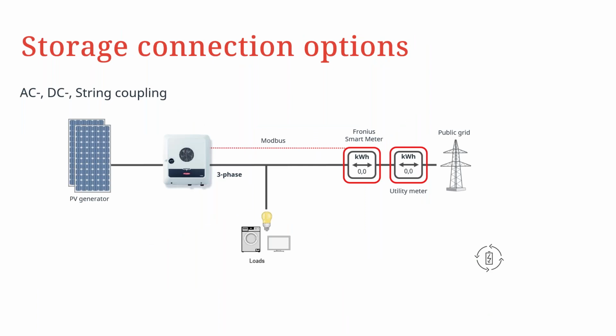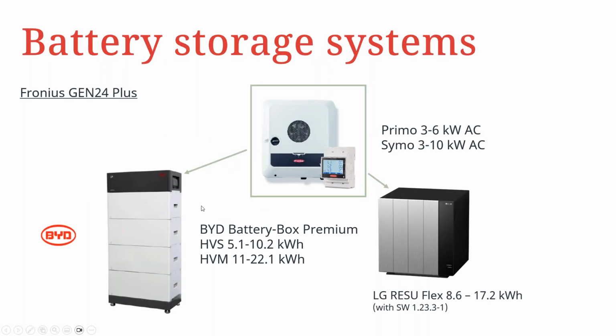So for storage connection options, first off, we have to note that the GEN24 Plus inverter is a PV inverter, meaning that it uses DC as its control voltage. So once that is recognized, it of course converts the DC to AC as expected, and then has the dedicated terminal through which it can charge the battery. And then for the battery options, apart from the BYD battery box premium HVS and HVM, we now also have another compatible battery, which is the LG RESU Flex in power capacity of 8.6 to 17.2 kilowatt hours.